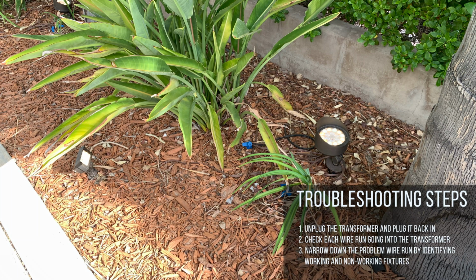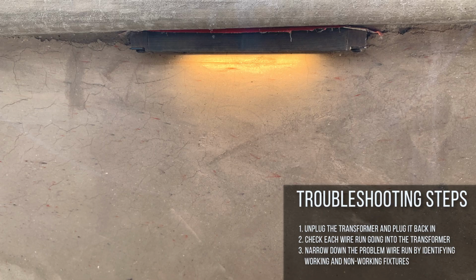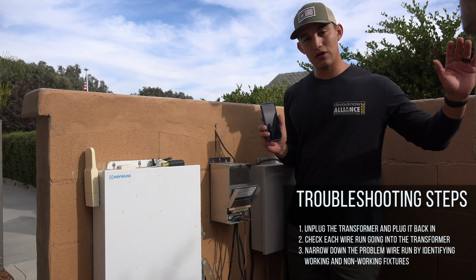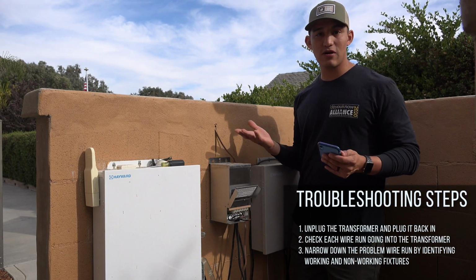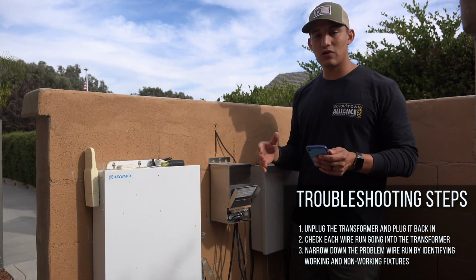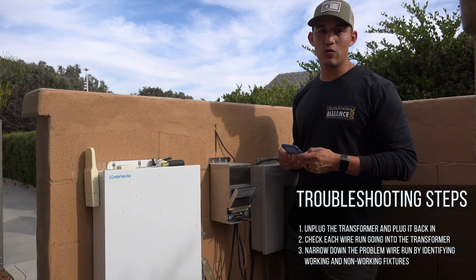So I know which wire runs are working and where they lead to in the yard. Now, to find the lead that's not working correctly, I'll go through the yard to the lights that are not on, and I'll start there. That's where I'll do my investigative work to find out where that trip is.